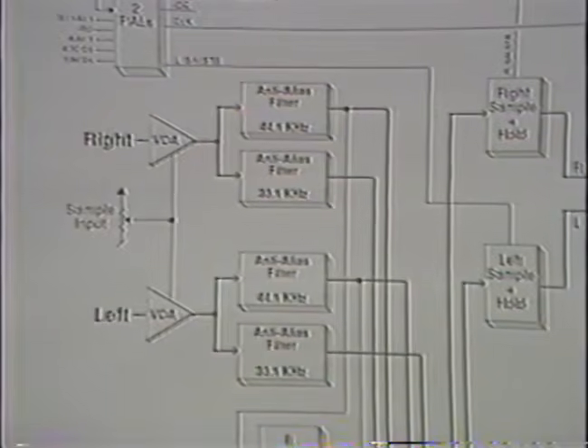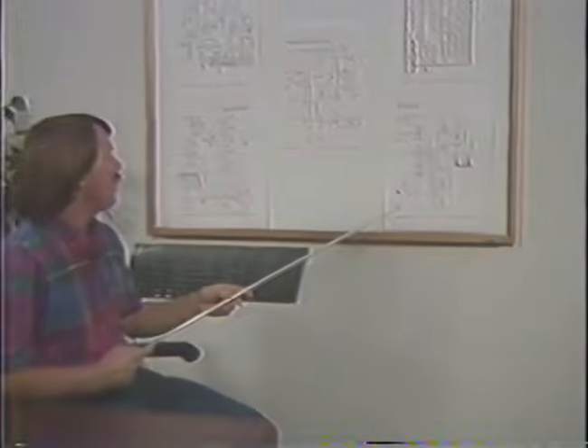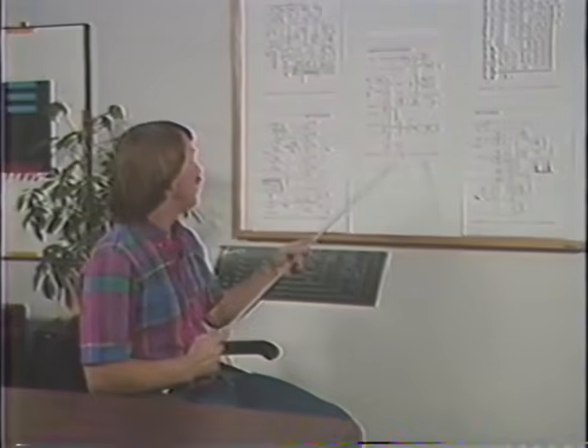Getting back into the analog circuitry, we come directly from the sample input jack into a pair of VCAs. We use VCAs here because this signal is terribly noise critical. We don't want to wire it through more wire than is necessary up to the front panel board and pick up digital noise there. The sample input pot directly talks to these VCAs and attenuates the signal there. It's then passed into the anti-aliasing filters, which are a pair of laser-trimmed elliptical filters, and those come into the separate channels which are selected at these analog muxes. That's pretty much it for the ADC board. The last board that we have to talk about is the output board, of which there are 2.